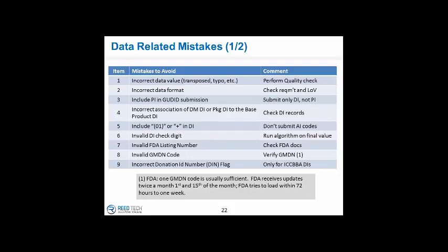We get numerous questions about that from those starting to go down this UDI trail. There are some fields in the record that talk about these production controls, but they're simply yes or no. Do you make use of a batch number for process control? Do you make use of a serial number? And that's yes or no. The actual serial number is not recorded, so just keep that in mind.